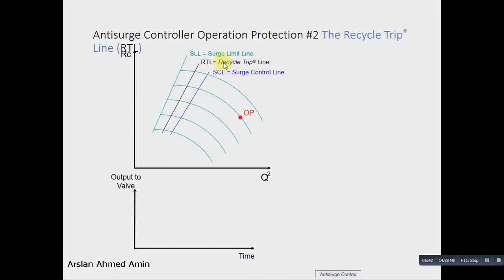This operating point, when it touches the RTL, there is a quick response. When it touches the surge control line, the response is PI response. But since the operating point is coming very fast towards the surge limit line, we need to open the recycle very quickly. Because if we do not do this, the point may cross the surge limit line. In order to protect it, we have defined another line, which is the recycle trip line.